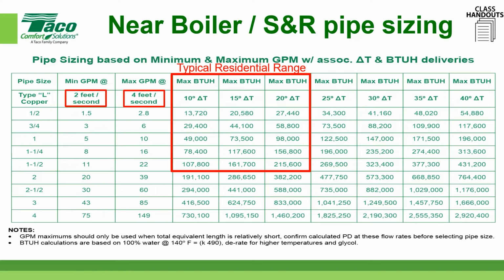And again, this is something I've used years before I even was working with Taco. It's not anything that's based on Taco. It's just general rules within our industry. So use it if you want to. Okay. What I did here is I just wrote in the ASHRAE rules. The 4 foot of head per 100 foot rule is right next to here, because when you get up into these bigger sizes, you can save yourself some money by not trying to look for 5-inch pipe because you had a 200 gallon per minute requirement. You know what I'm saying? So you can go up to 270 and still be at 4 foot of head per 100 foot, and that's an accepted ASHRAE standard.